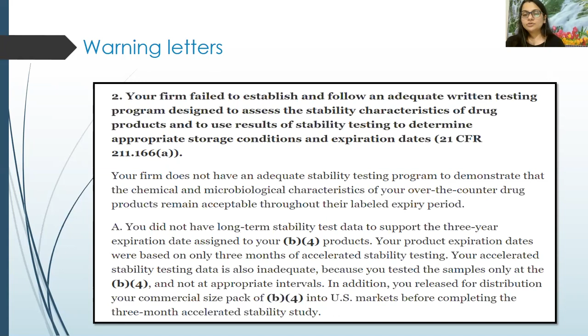A. You did not have long-term stability data to support the 3 years expiry date assigned for your product. Your product expiry dates were based on only 3 months accelerated stability testing. Your accelerated stability testing data is also inadequate because you tested the sample only at the initial point and not at appropriate intervals. In addition, you released for distribution your commercial size batch in the US market before completing the 3-month accelerated stability study. So friends, don't take it otherwise. You can see on the FDA site which type of observation related to stability study can be found.